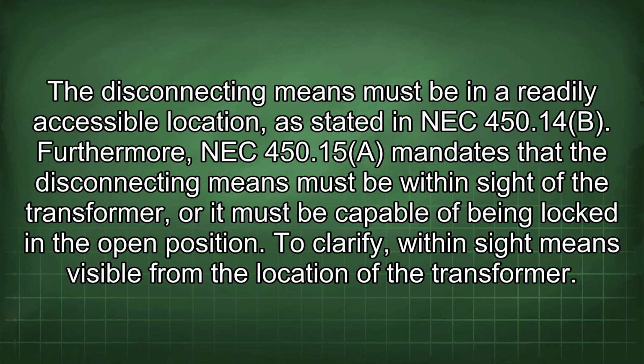The disconnecting means must be in a readily accessible location, as stated in NEC 450.14(b). Furthermore, NEC 450.15(a) mandates that the disconnecting means must be within sight of the transformer, or it must be capable of being locked in the open position. To clarify, within sight means visible from the location of the transformer.